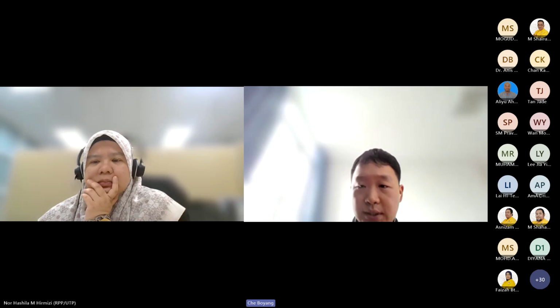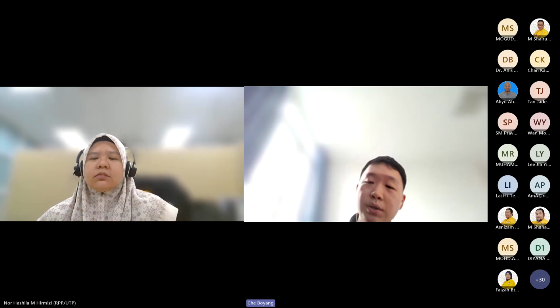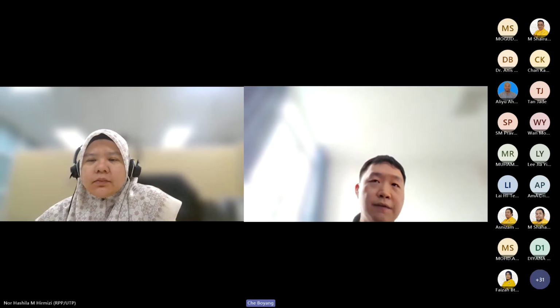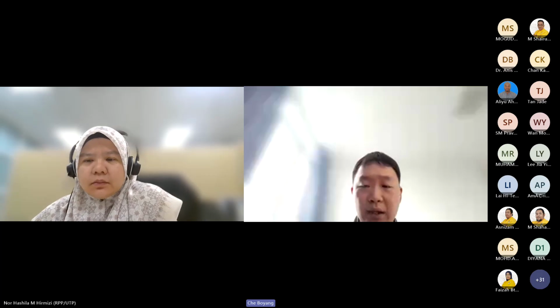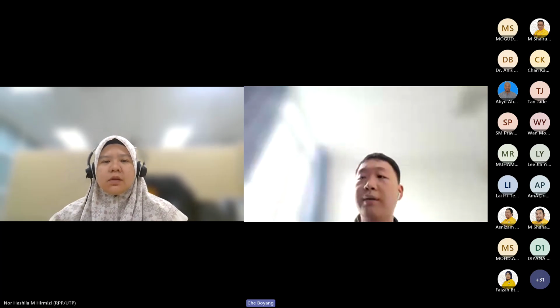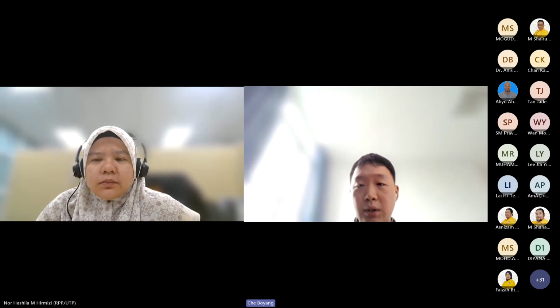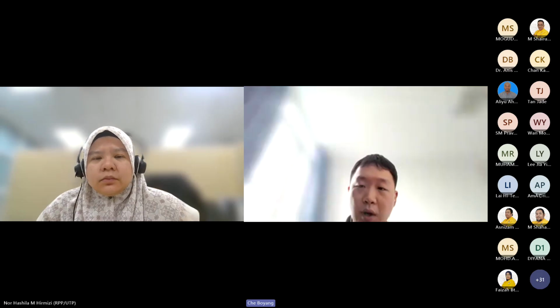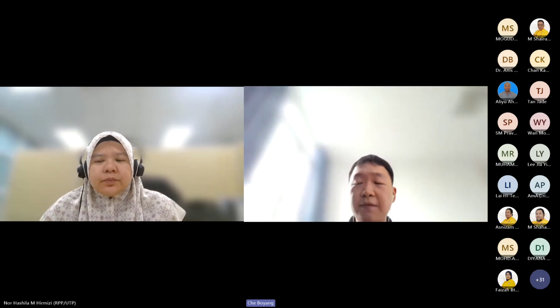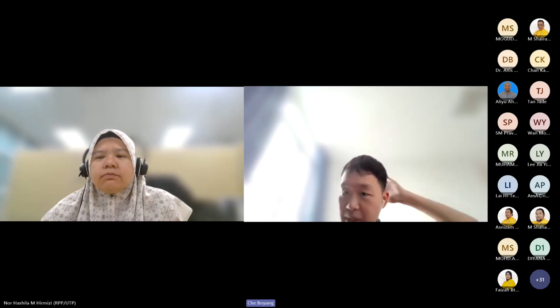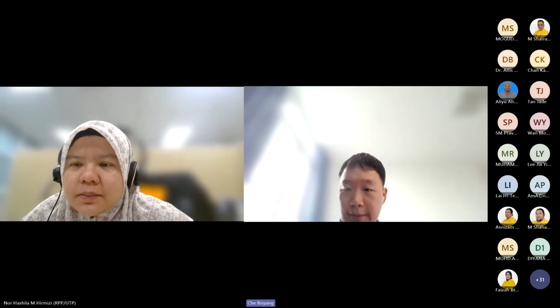And the second point is, on the new system, we have a function called smart sampling, which is an algorithm to help you increase your measurement speed for mapping. Under smart sampling, we are not scanning from the first point to the last point, or from left to right. Instead, we start scanning from those points with more contrast, and more contrast means more features. So we scan those points with more information first, and then fill in the details of your image. By running smart sampling, you can get your Raman mapping much faster, and you get the main information first. So that's my comment on the speed of scanning for Raman imaging.